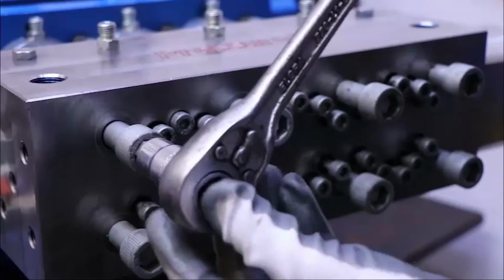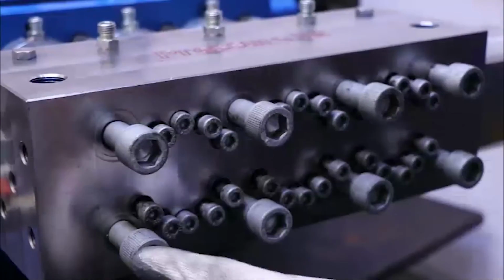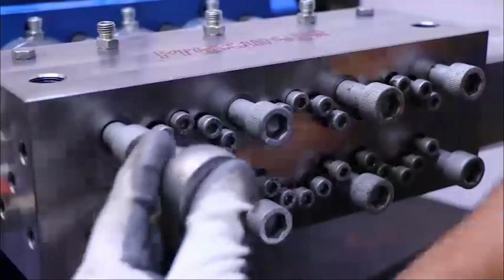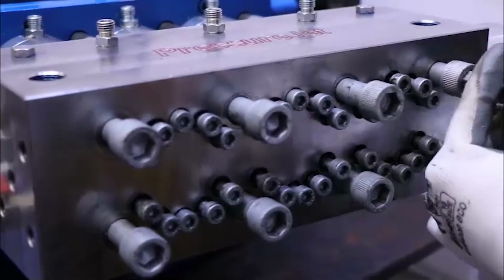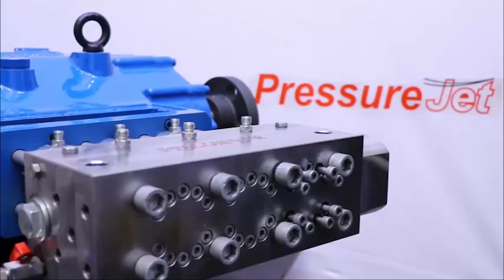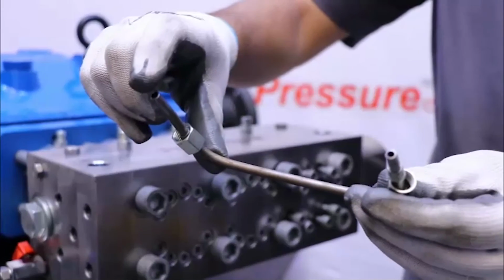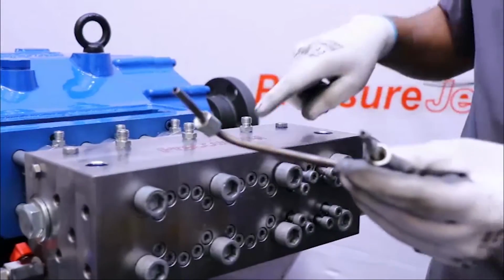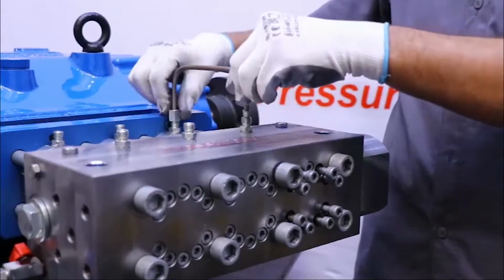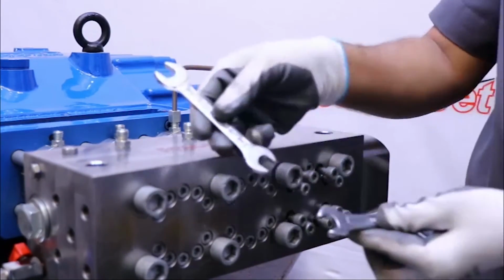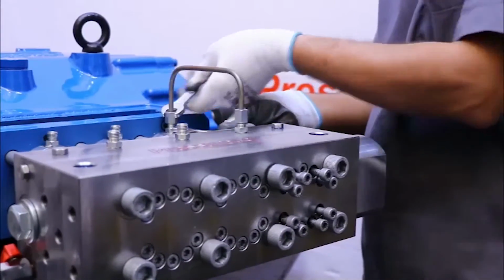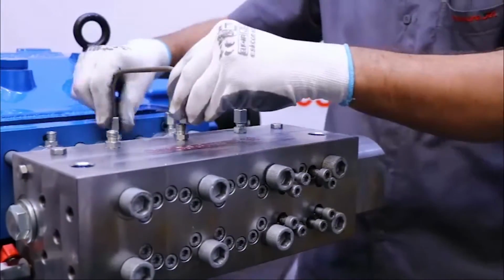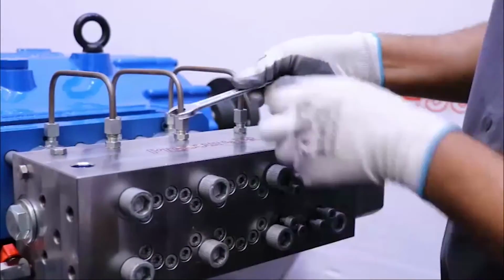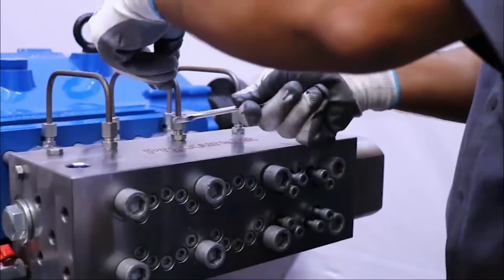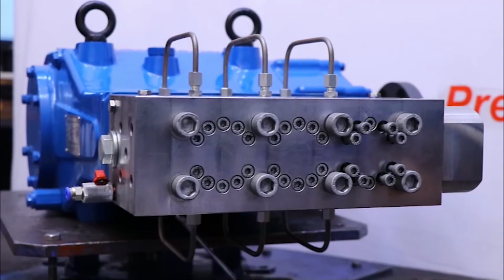Now gently tighten all screws using an Allen key socket and wrench in a diagonal way. Now assemble all 3 cooling pipes at the top and screw them onto the top side ferrule connection in such a way that the longer end connects with the stuffing box and the shorter one with the pump head, using a 6 mm spanner. Same as the top, assemble all 3 bottom cooling pipes.